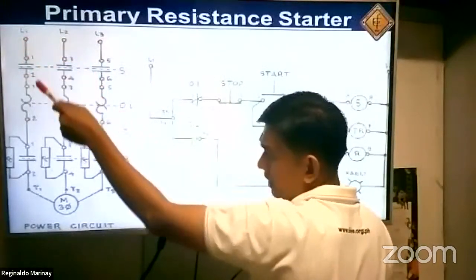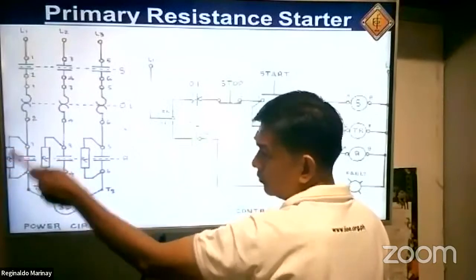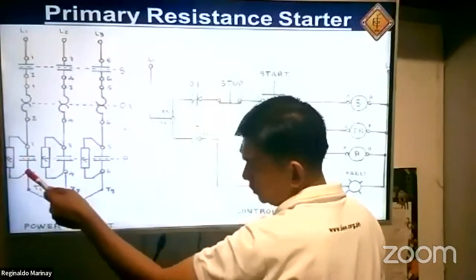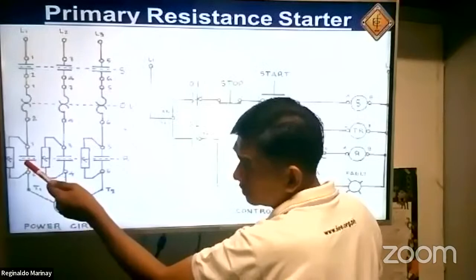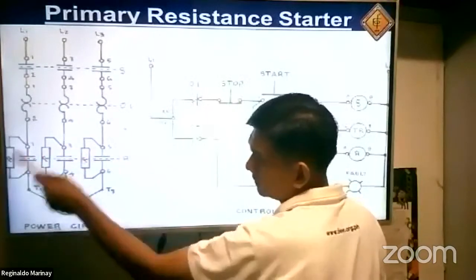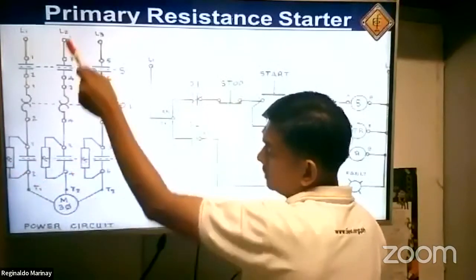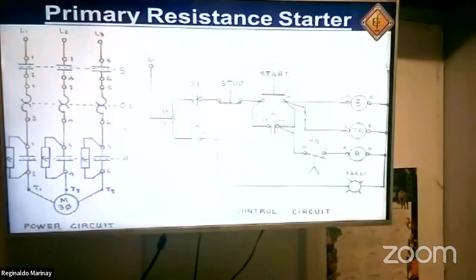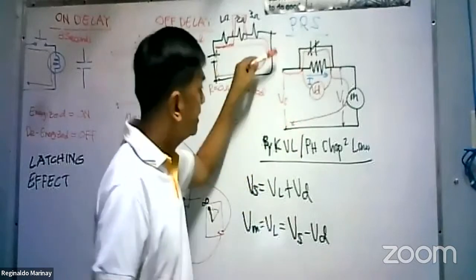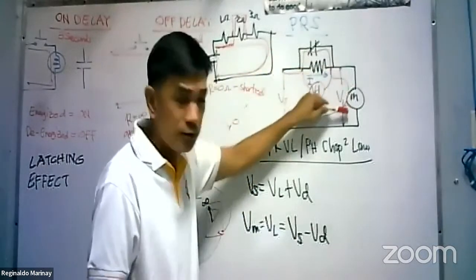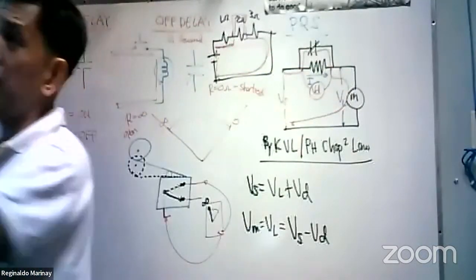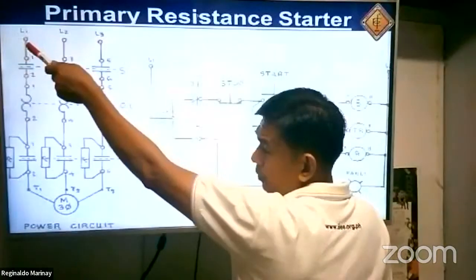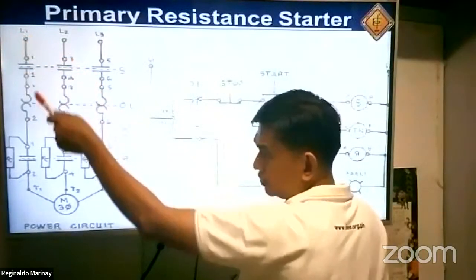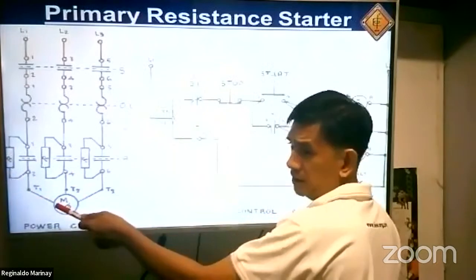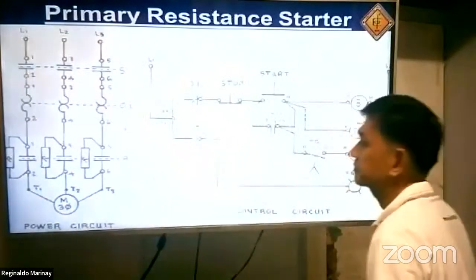Once this becomes energized, all at the same time, the current will flow here. Take a look here. The current will flow to your resistance unit, right? Because this is an open circuit. It will go to the resistance unit, just like our example before. Initially, from 0 to 2.99 seconds, the current will flow to the resistance unit, going to the motor. Also, the same thing here. The current will flow from the source, going to the resistance unit, going to the motor. That's the idea.